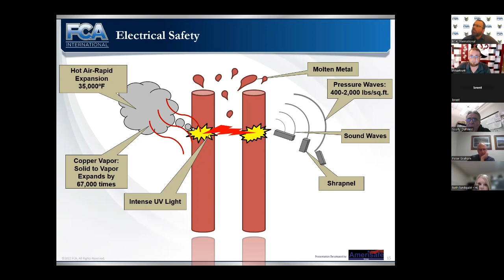Train your employees to the hazard. Empower your foreman to refuse to work near unsecured panels. Document your communication with general contractors. If they give any pushback, make sure panels are appropriately guarded, meaning they have dead fronts on. The dead front is what you see when you open your circuit breaker panel and don't see any wires. If you're not seeing any wires, the dead front is on.